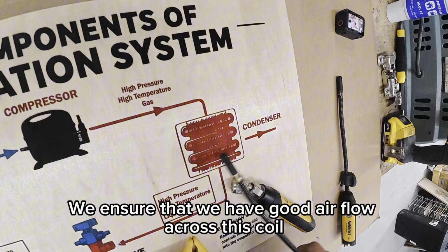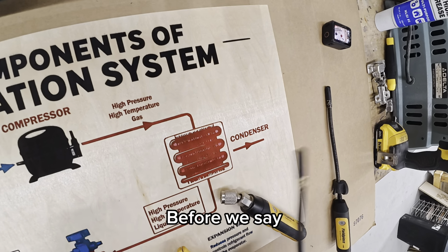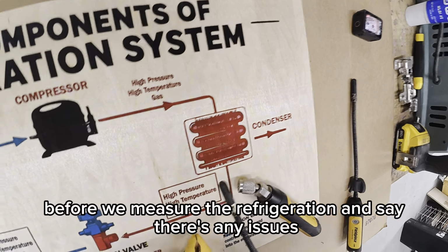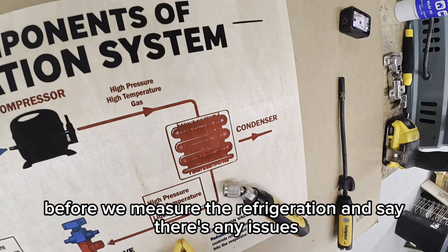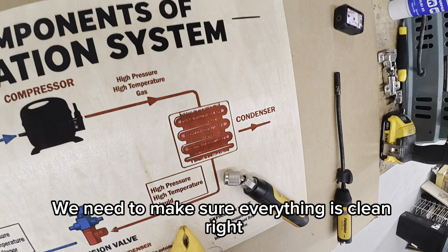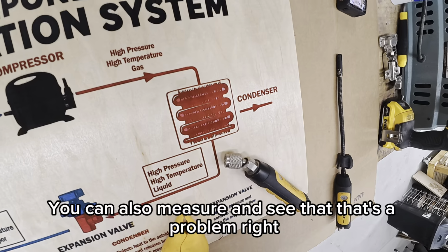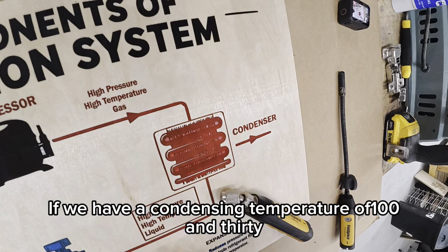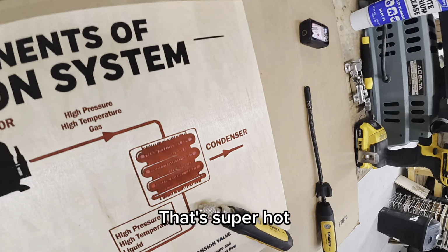We ensure that we have good airflow across this coil before we say any judgment on refrigeration. Before we measure refrigeration and say there's any issues, we need to make sure everything's clean, right? You can also measure and see that that's a problem, right? If we have a condensing temperature of 130, 140 degrees, that's super hot.